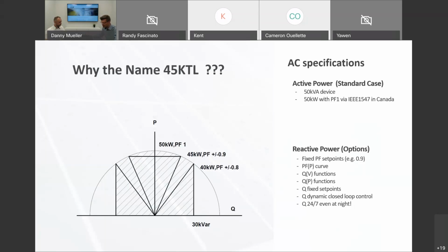I've put the PQ diagram here on the slide, and we're operating exactly at unity power factor on, in this case, the y-axis. The unit, however, is able to provide up to 30 kVAR reactive power, and that reactive power can be used in a multitude of applications, which are not the standard application for a grid-tied solar system, but in a microgrid scenario, for example, or if you have a power factor correction requirement, or some utility companies want to have your bigger system supporting the grid in a more advanced feature, similar to a grid code like the California one, then the inverter can already do that, and is in this regard future-proof to changes in the grid code.